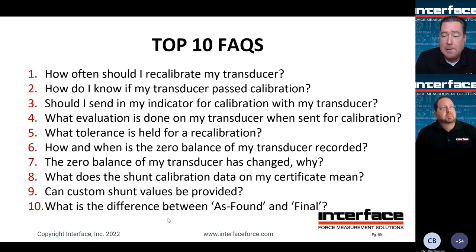Let's say it's a hazardous environment for the load cell and it's being used perhaps past its design considerations. Perhaps that's a load cell that should be put on a shorter interval so you can track its performance, and if something's going wrong with it, you capture it sooner. Or if it's a critical measurement, tighter intervals will promote confidence in the measurements you're getting from the transducer. If it's a calibration type environment, of course, default to ASTM E74 for justification of that calibration interval.